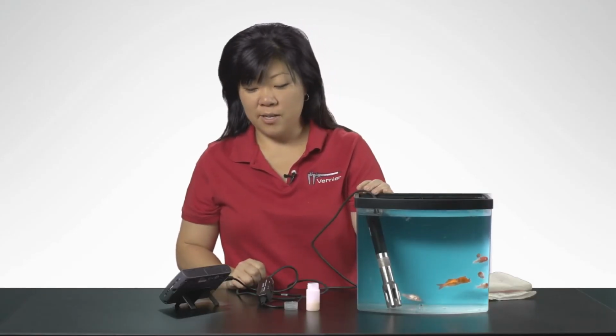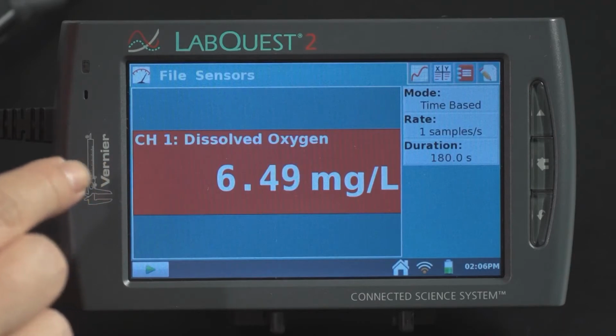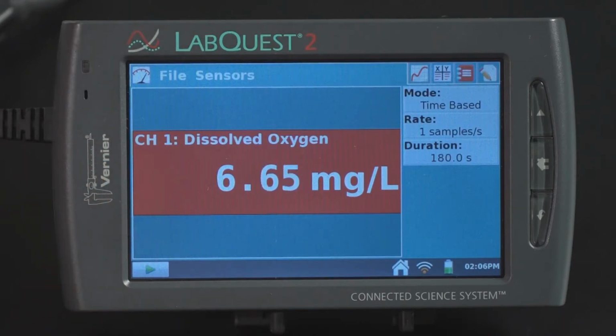The reading of this fish tank is reading approximately 6.4. It will take 40 seconds for the DO probe to reach 90% of its final value. So you may want to wait a few minutes for this value to stabilize.